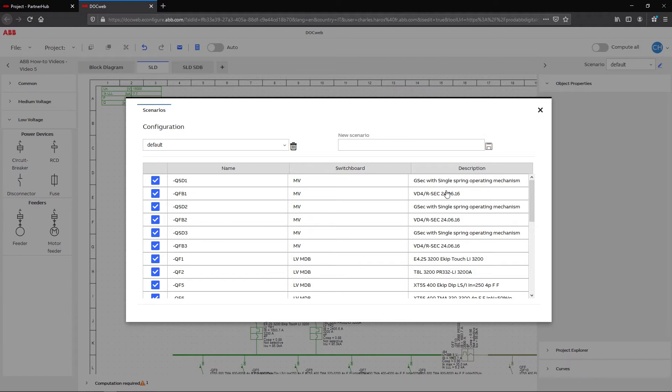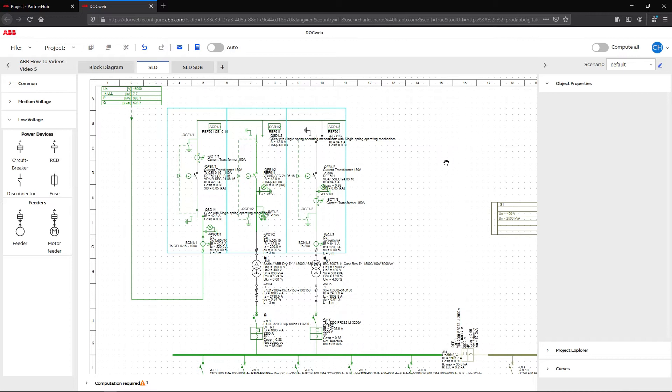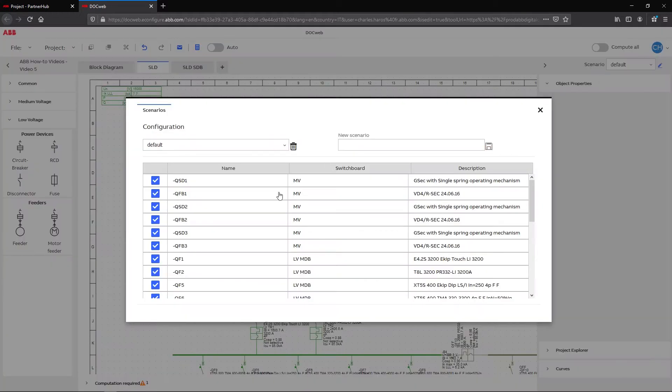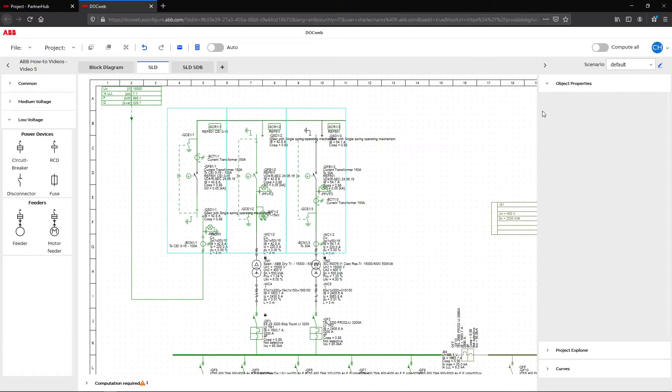In our case, we want the second feeder not energized in normal operation. To do so, start by identifying the breaker name on the sheet. Then on the default scenario table, simply uncheck the QFB3 breaker and close the scenario window.